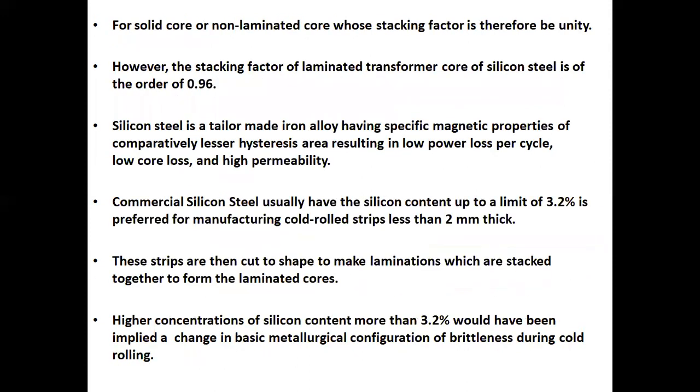For a solid or non-laminated core, the stacking factor is unity. However, the stacking factor of a laminated transformer core of silicon steel is of the order of 0.96.